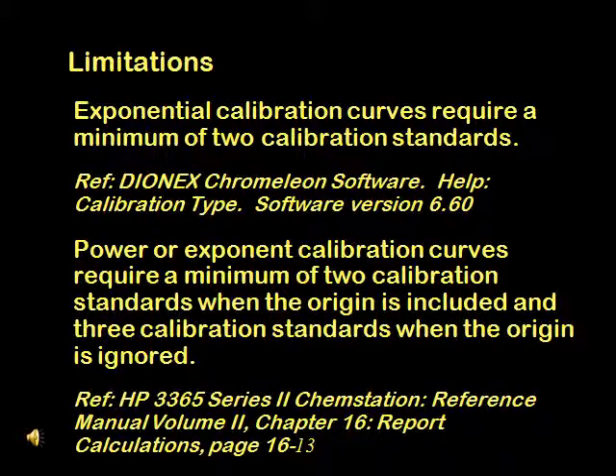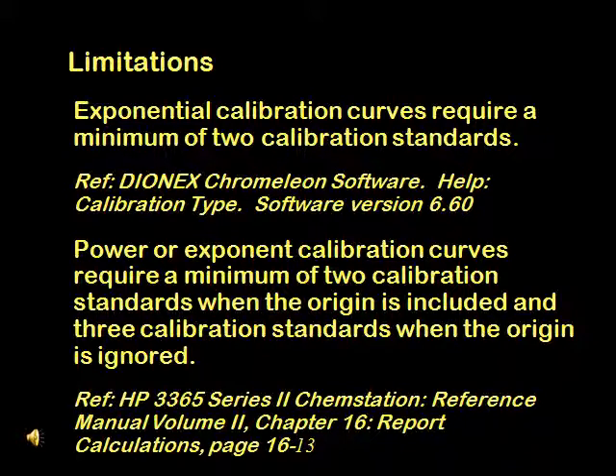There are limitations to the use of power and exponential calibrations. The exponential equation requires a minimum of two calibration standards. In addition, power and exponential calibrations require a minimum of two calibration standards when the origin is included and three calibration standards when the origin is ignored.